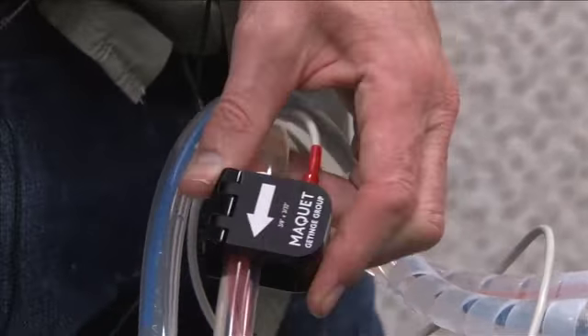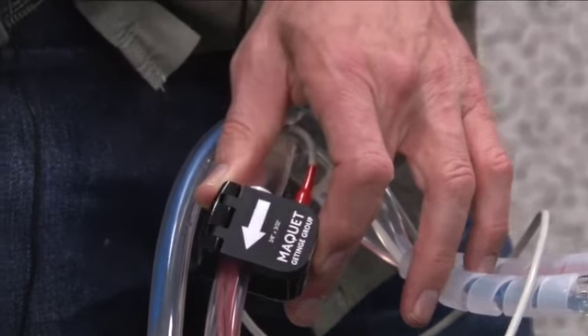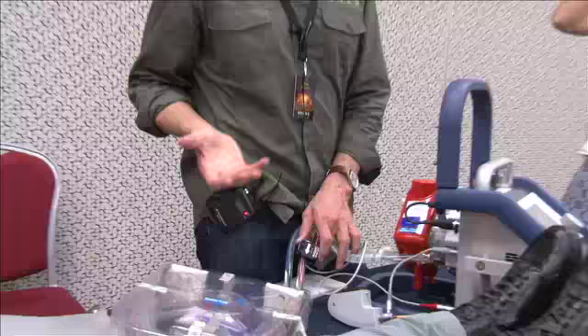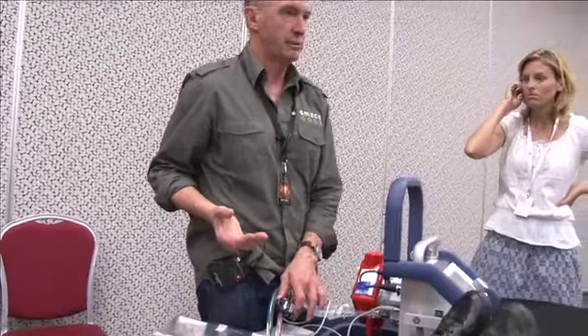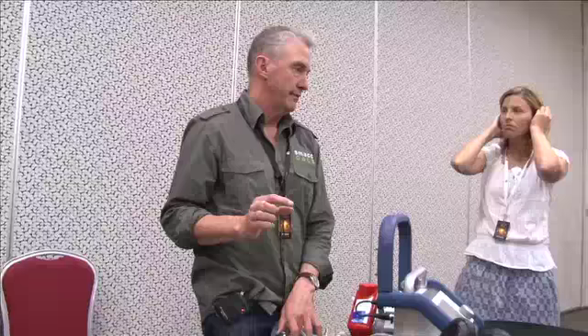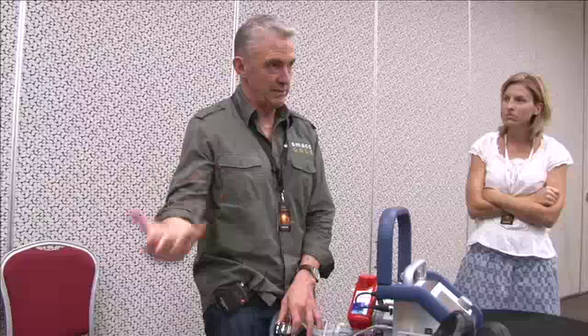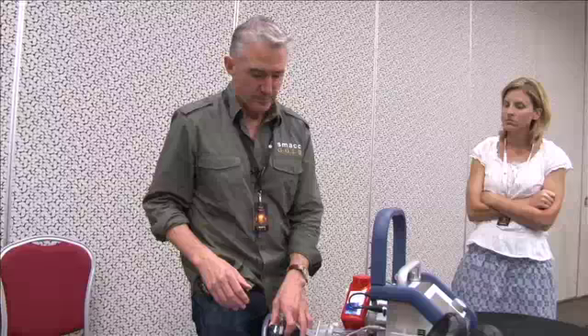So it'll tell you if there's an air bubble in the circuit. The ECMO software shouldn't stop the pump in response to that, though. These pumps can be used as heart-lung machines in cardiac operating theatres. If there's an air bubble from the surgical field, the pump needs to stop in response to that, so you're not producing a massive air embolus back to the patient. But for an ECMO patient, these bubbles are likely to be very small, and while you might want to know about them, you don't want the pump to stop under any circumstances, because if it does, in VA cases, you're going to have acute backflow through the circuit.